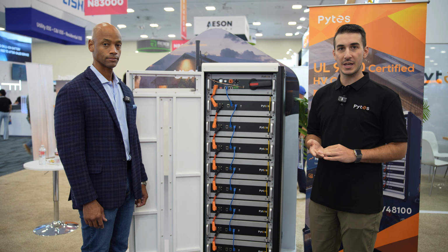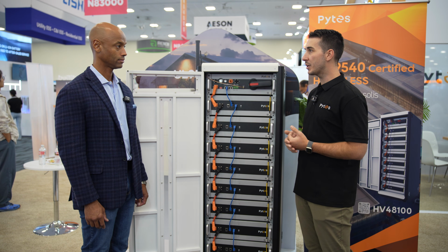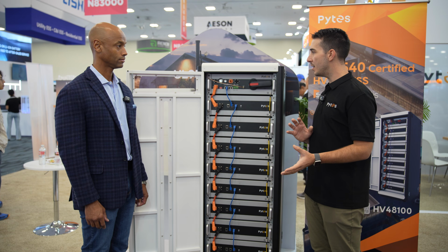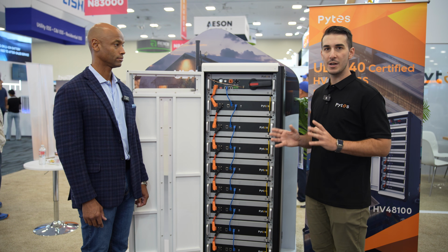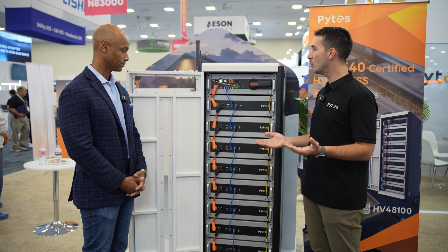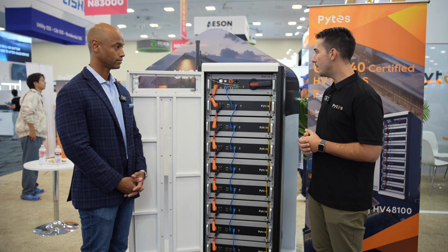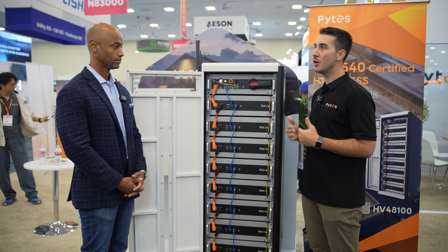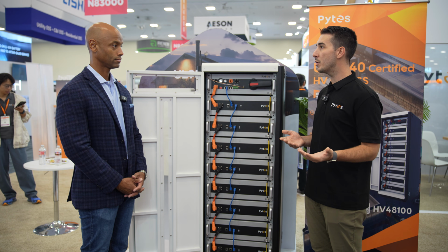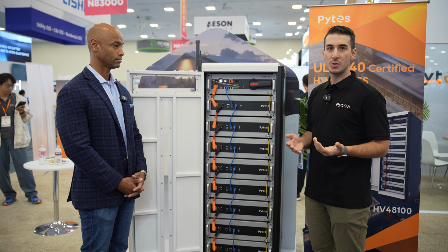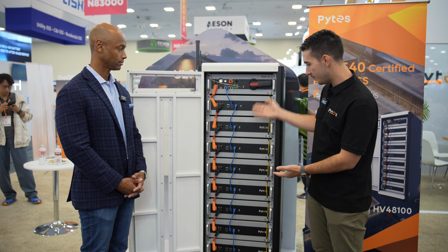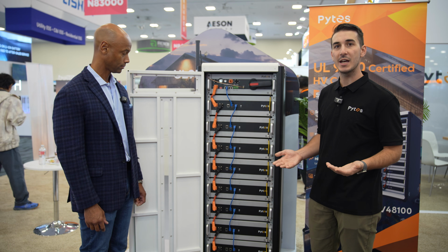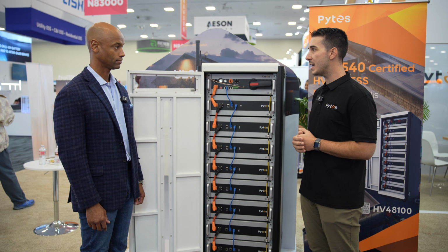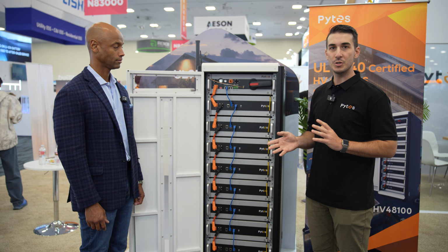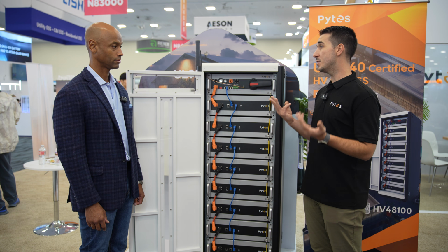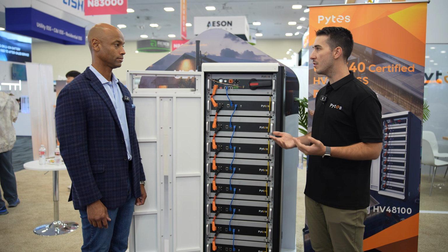Certification with the Sol-Ark 60K is coming in the next few weeks. In terms of what kind of application you would find this being used in, this is getting into the small scale industrial or commercial space. An example with the Sol-Ark 30K, let's say, where the need for power output in kilowatts isn't all that high, but you do need a three-phase 120/208 AC output. In that case, you can use our high voltage solution, a cabinet, for example, with anywhere from 6 to 8 modules connected in series. That pairs perfectly with the Sol-Ark 30K, and now we can get that three-phase 120/208 AC output with just one single inverter instead of having to use 3 inverters like you would with their 12K or 15K low voltage models.